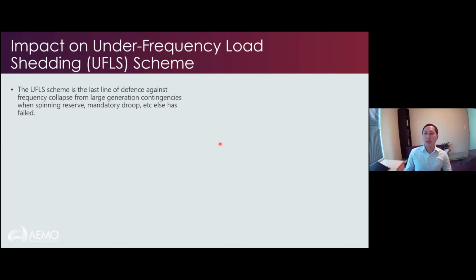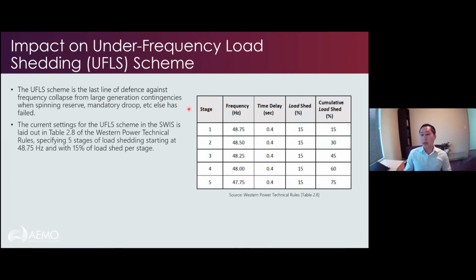So the next issue is really on the impact of DER on under frequency load shedding. So the UFL scheme really is the last line of defense when frequency collapses from big generator contingencies, and when all of our primary frequency response, spinning reserve, droop, etc., has failed. And in the SWIS, the UFL scheme is laid out in Western Power's technical rules, in 5 stages at these frequencies, and they're 15% blocks, so they're uniform blocks.